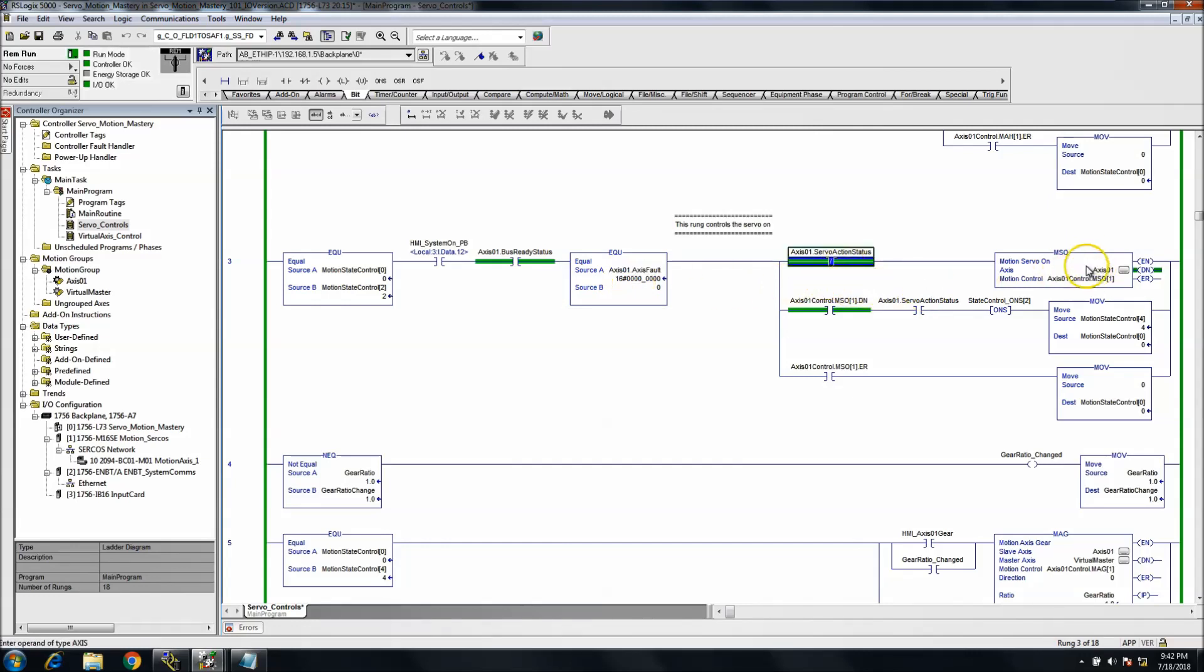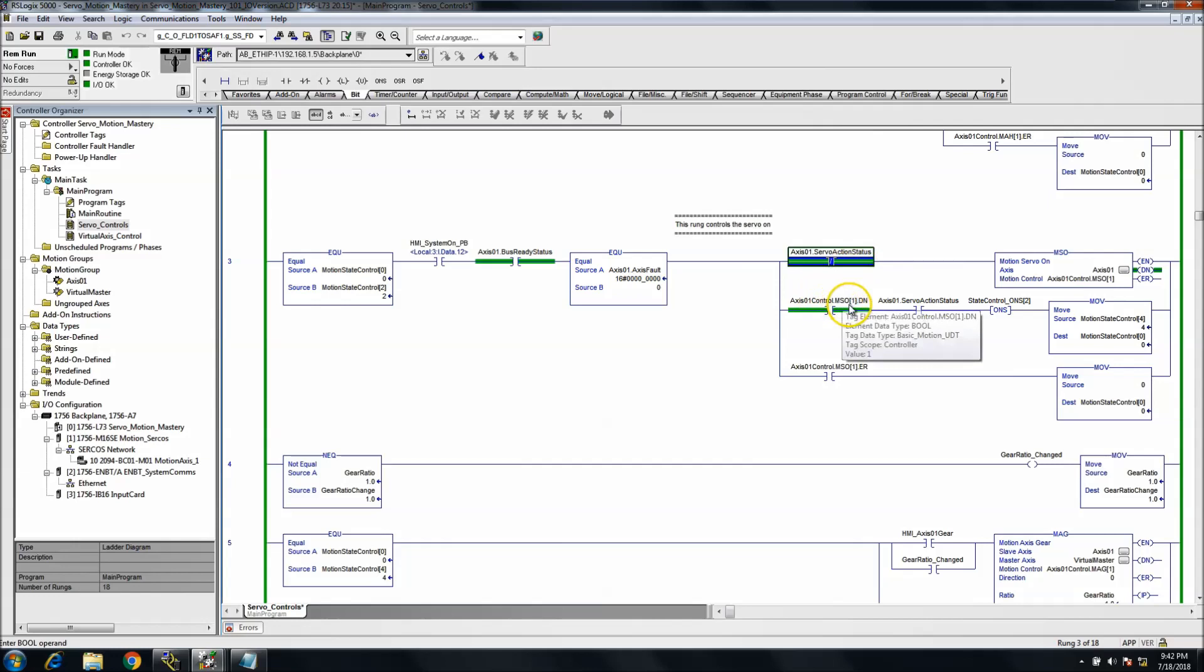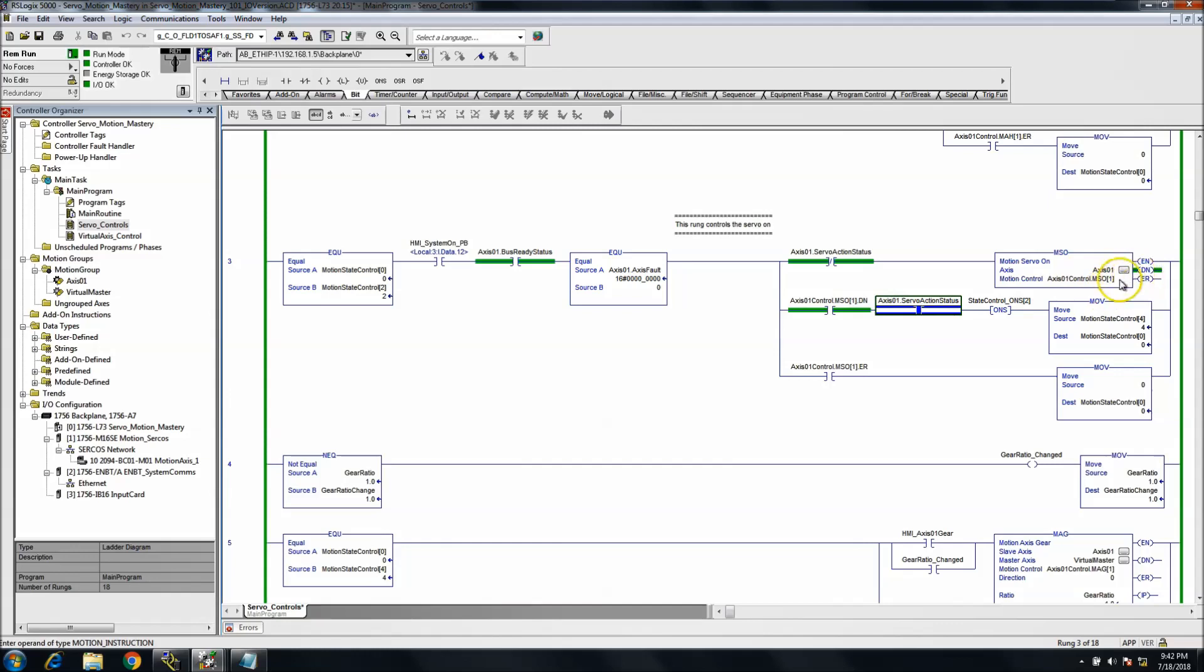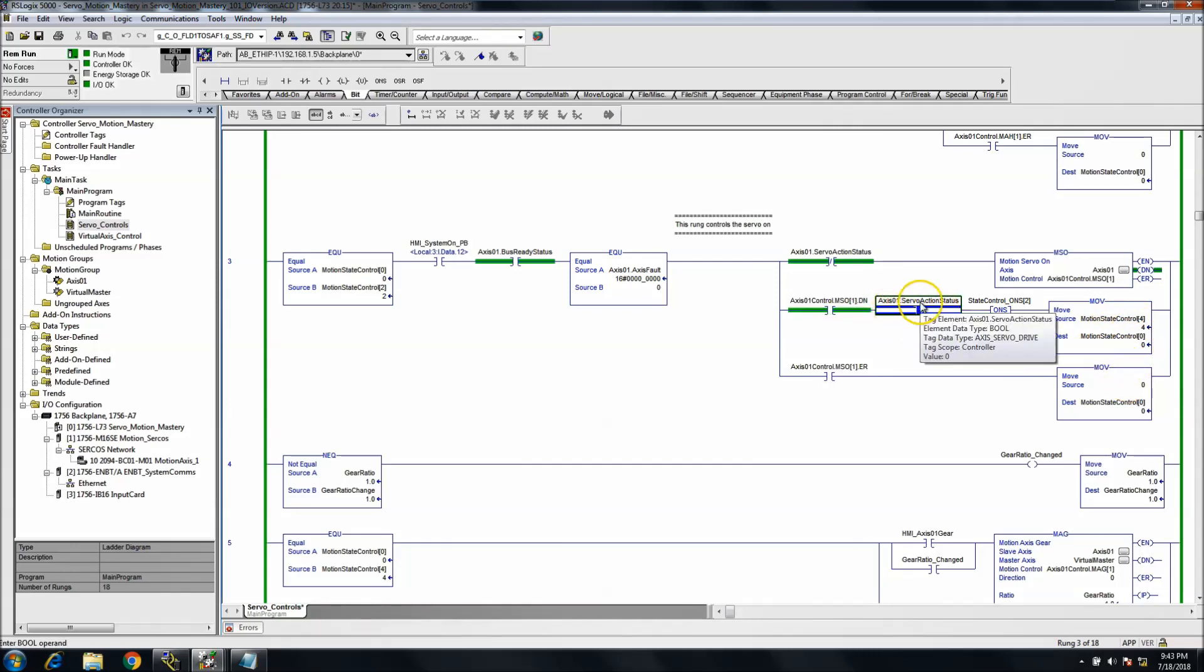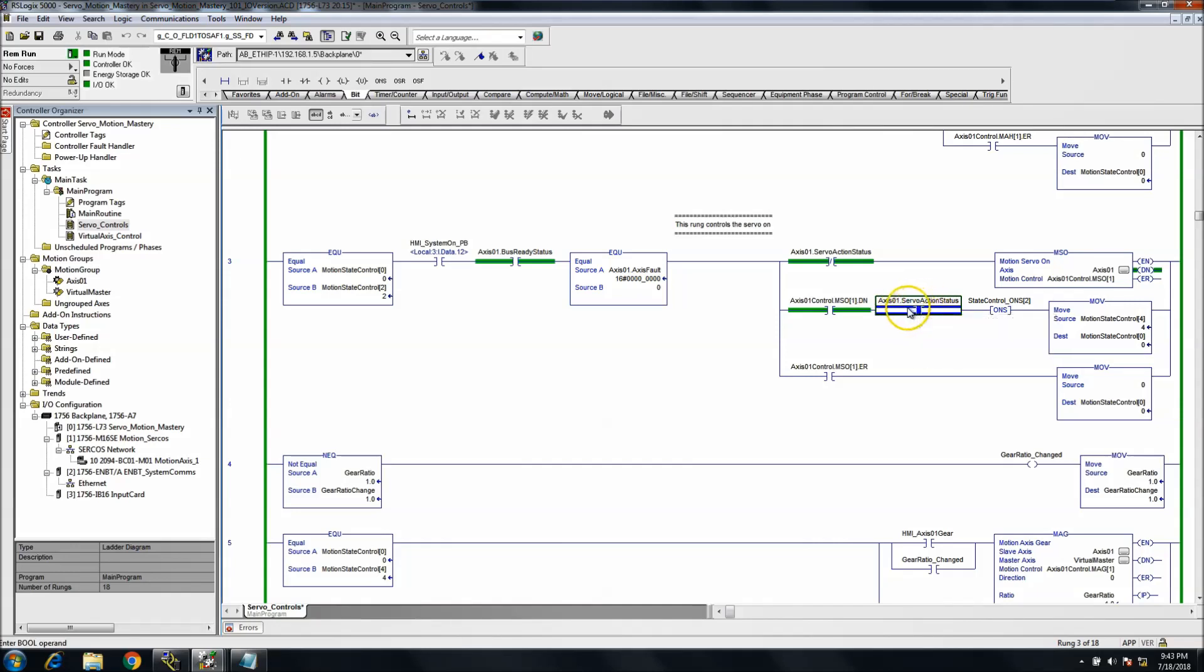I like to cut it ON and I'm not going to keep issuing an ON statement. As soon as it cuts ON, the axis status bit will come ON and this will only issue one time. As soon as the motion axis servo ON is done, I want to issue it to the next controlled state, but I don't want to do that until the axis is truly ON. So I look at the motion or the servo axis status.